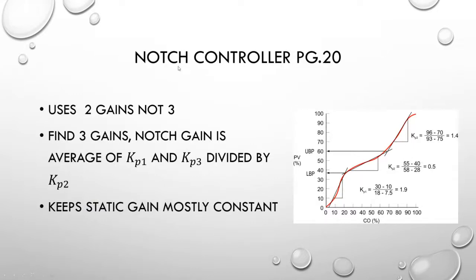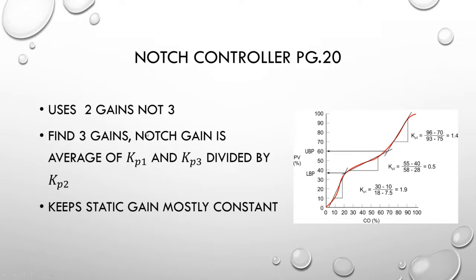Here's one called a Notch Controller, incredibly similar to the previous example. The difference comes down to using two gains instead of three. We find three gains just like in the previous example, and derive something called the Notch gain, which is an average of KP1 and one gain divided by another gain. It gives us a number we can multiply our controller gain by in order to make a consistent operating gain applied throughout the operating range. This keeps the static gain mostly constant.